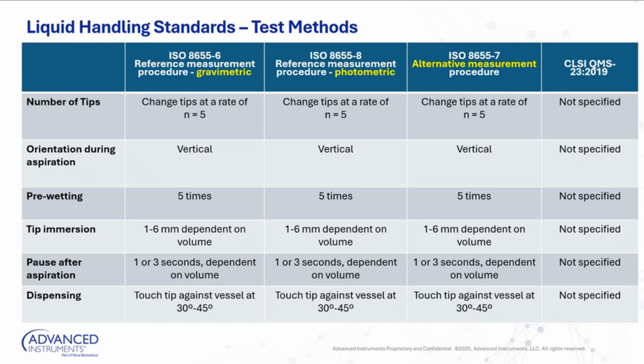The very first technique that we see here is the number of tips that are used. According to ISO 8655, Parts 6, 7, and 8, they recommend that you change tips at a rate of n equals 5. That means after 5 replicates, you change your tip. So those of you that answered 2, 5 times 2, right? Because we've got 10 data points that we're taking, you're absolutely correct. You can give yourself a little pat on the back. All right, let's go down a little bit further and take a look at the rest of these techniques. These are not all inclusive, but these are some of the ones that I wanted to specifically call out to you.